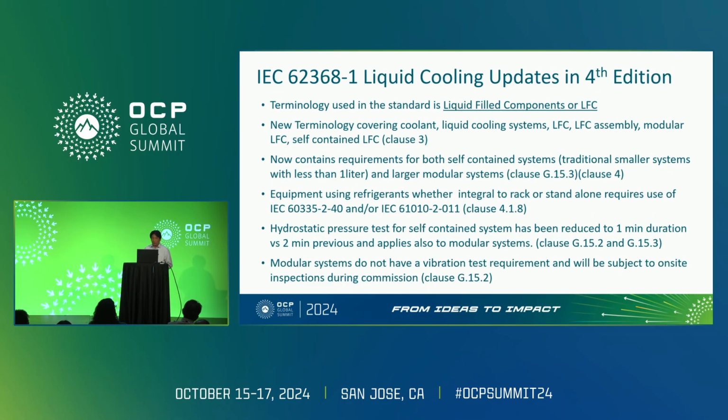Now, getting into the liquid cooling side, I was able to extract a few items from the 4th edition, which is a lot more clear now. The terminology they use in the standard is liquid filled components, or LFC. So if somebody in the standard world says LFC, you know that involves liquid cooling. There are new terminologies covering coolants, liquid cooling systems, LFC, LFC assembly, modular LFC. These are all terminologies that are now defined in the standard. It also contains requirements for self-contained systems, either traditional smaller systems, less than a liter, or larger systems, and also provides some differentiation based on the amount of fluid that you're using.